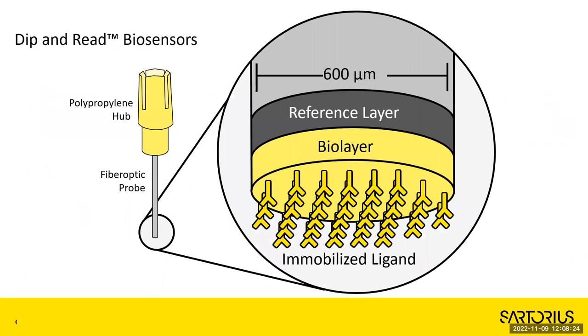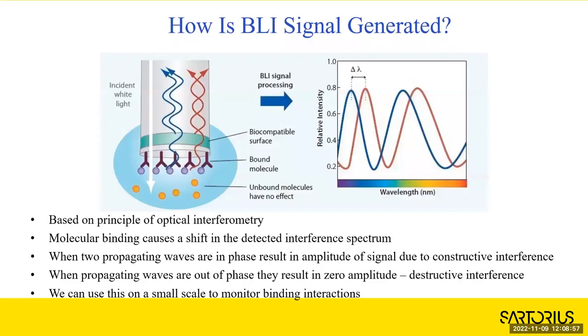These are the different biosensors - they come in a number of chemistries, things like streptavidin, protein A, protein G, and nickel. They're about the size of a small pipette tip. On the very tip is a reference layer followed by the biolayer. White light is shot down through the tip of the biosensor, and when it dips into the well of a 96-well plate, things can start binding to it. Part of the light bounces back off the reference layer at a specific wavelength.